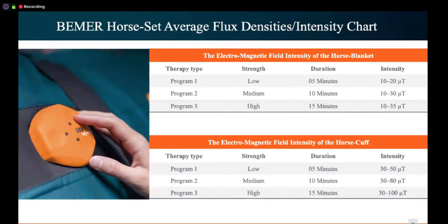But when you take a look at the actual cuff, you have the same scenarios, programs low, medium, high, same time duration, but you are basically 3 times stronger than the blanket. So they all start out again at 30, and 5 minutes goes to 50, then 2 goes to 80, 3 goes to 100 microtesla.